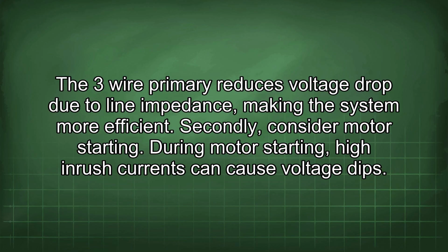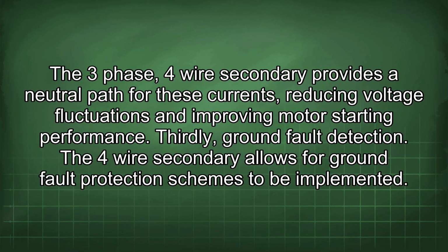Secondly, consider motor starting. During motor starting, high inrush currents can cause voltage dips. The 3-phase, 4-wire secondary provides a neutral path for these currents, reducing voltage fluctuations and improving motor starting performance.